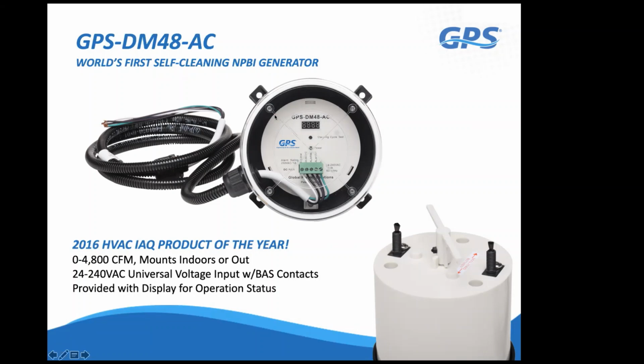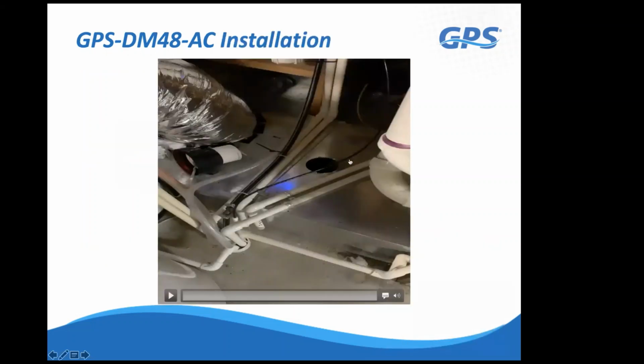But you can actually remove it from the duct. You take this clear cover off, and then with a 3/4 turn twist, this white part will pull out of the duct. And here's what it would look like. You simply drill a 4-inch round hole, drop that canister into that hole, and then 4 sheet metal screws hold the black part of the housing onto the duct permanently. That allows you to take the white can in and out of the duct in order to inspect it from time to time, since you cannot see the wiper blade once it's installed. But generally, if there is a fault in the stepper motor or any issues with the circuitry, it's going to say fault on the display.